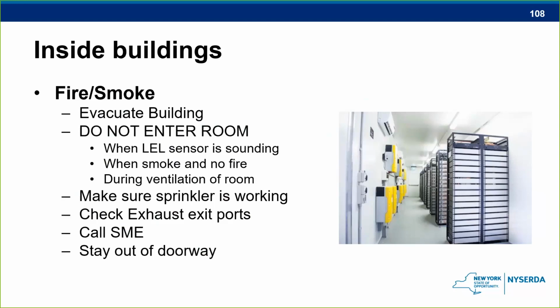We do not want you to enter that room during the ventilation of the room. So if this thing is kicked on, what happens if we're above the upper explosive limit? We could be bringing it down into the just right area where we could have explosions. So we want you to really kind of stay out of the room when there is no fire showing. If there is fire showing, well, guess what? It's consuming any of that off-gassing that we're concerned about.